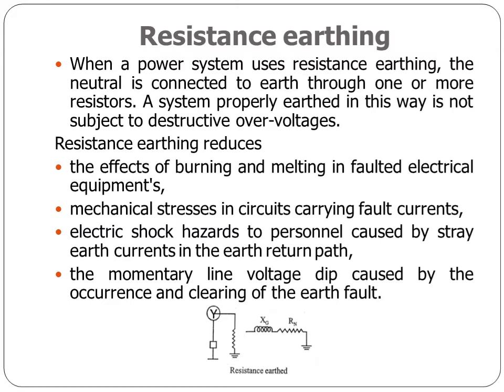Next one is resistance earthing. When a power system uses resistance earthing, the neutral is connected to the earth through one or more resistors. A system properly earthed in this way is not subject to destructive overvoltage.